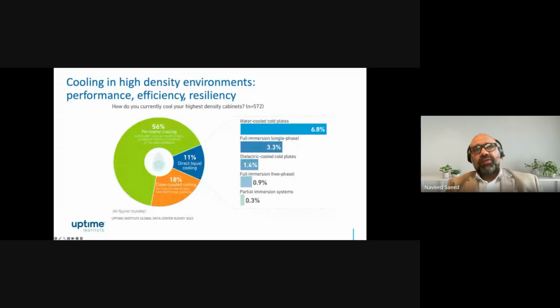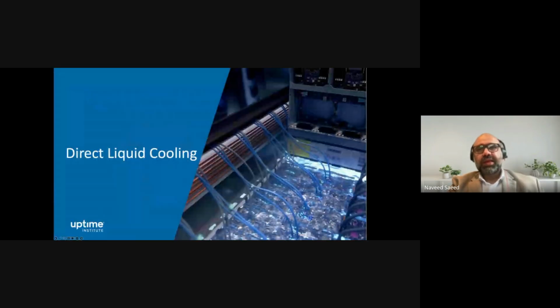And if we break down the 11% further, the water-cooled cold plates are 6.8%. Single-phase full immersion is about 3.3%. Dielectric cold plates are 1.4%. Full immersion two-phase is less than 1%. And partial immersion systems are 0.3%. Now, they are all different types of cooling technologies that are employed in data centers by different users to test the efficiency of cooling systems and to test the heat rejection capabilities.